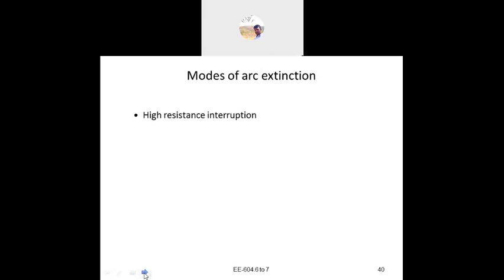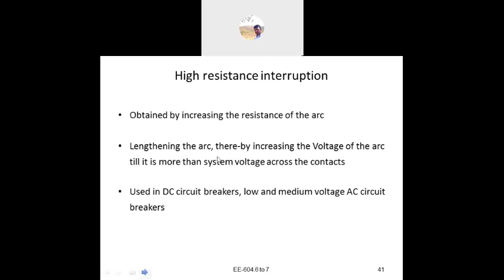So modes of the arc extinction. Which types of modes are we using? That is high resistance interruption, low resistance, or current zero. In high resistance interruption, the extinction is obtained by increasing the resistance of the arc and lengthening the arc, thereby increasing the voltage of the arc till it is more than the system voltage across the contact. This type is used in DC circuit breakers and low and medium voltage AC circuit breakers.